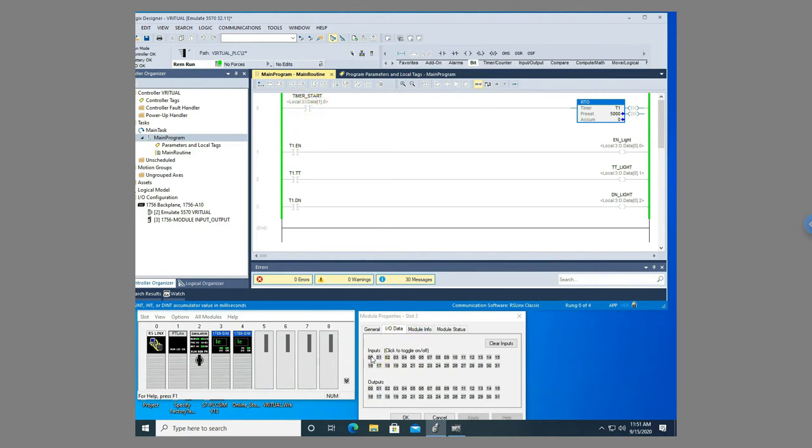But with one exception, let's say that I push this for 2 seconds, I let off. Notice what happens. It holds our accumulator value. That's why it's called a retentive timer on delay. Notice our enable bit followed this. Our timer timing bit was on for that 2 seconds, but it went off. So if I continue on for another second, notice that timer timing bit came back on, enable bit. They're going to follow each other until my accumulator value equals my preset.